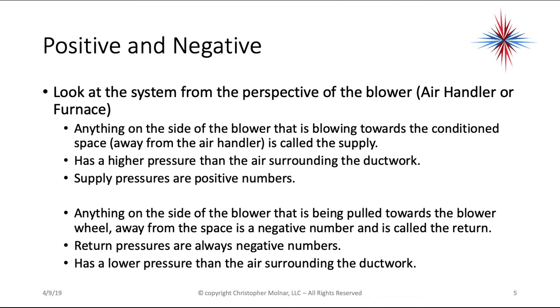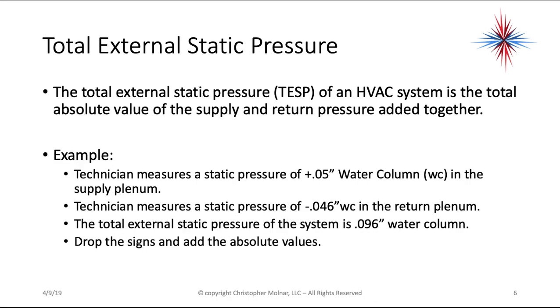Remember these positive and negative numbers because they will change your readings. The total external static pressure of an HVAC system is the total absolute value of the supply and return pressures added together — meaning you drop the sign and add them together. So a technician measures positive 0.05 inch water column in the supply plenum and negative 0.046 inches in the return plenum. The total external static pressure of the system is 0.096 inches of water column.